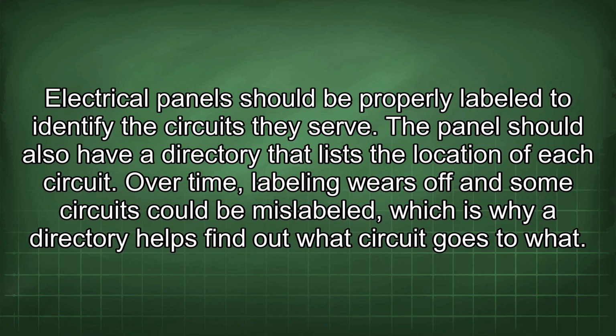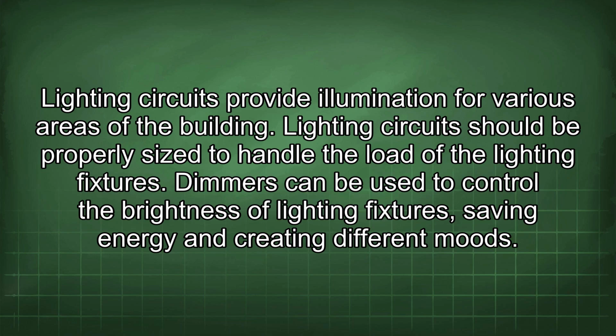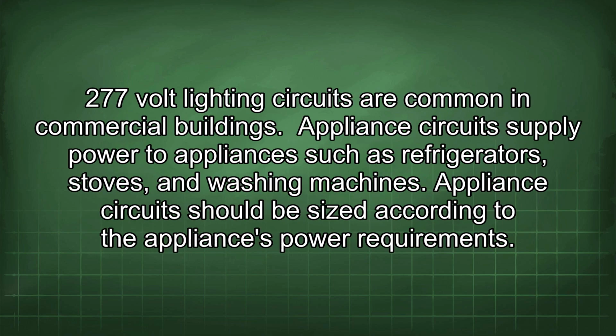circuit goes to what. Lighting circuits provide illumination for various areas of the building. Lighting circuits should be properly sized to handle the load of the lighting fixtures. Dimmers can be used to control the brightness of lighting fixtures, saving energy and creating different moods. 277-volt lighting circuits are common in commercial buildings.